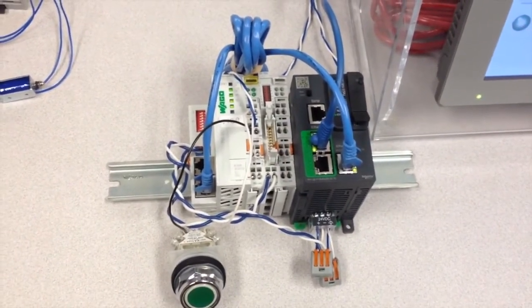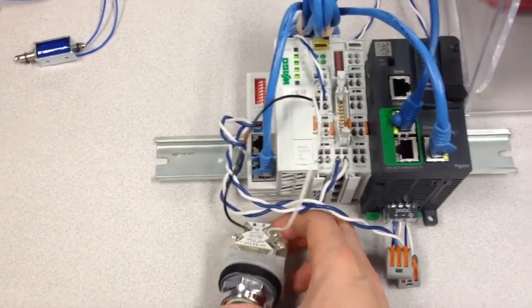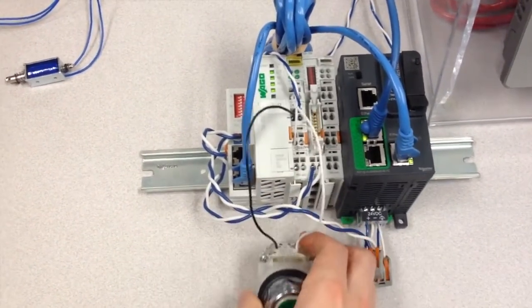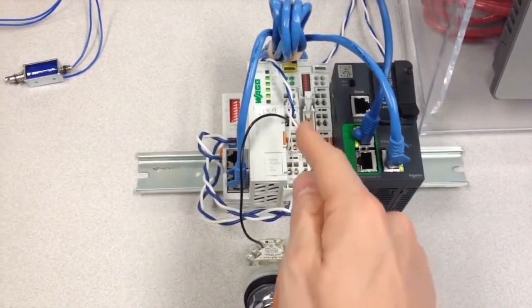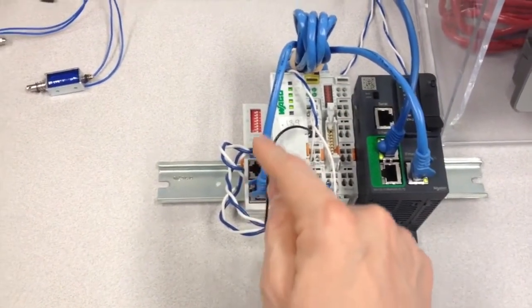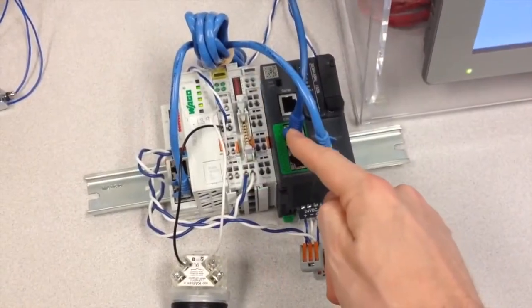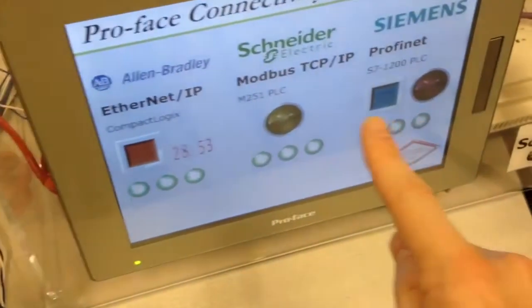On the WAGO PFC we have an input card and that is reading the status from this push button which is connected. Now once I press this push button, the signal will get transmitted digitally through the input card and then it will get transmitted over Modbus TCP into Ethernet 2 on the M251, and then it will get in turn sent out over Modbus TCP to the HMI and turn this lamp on.